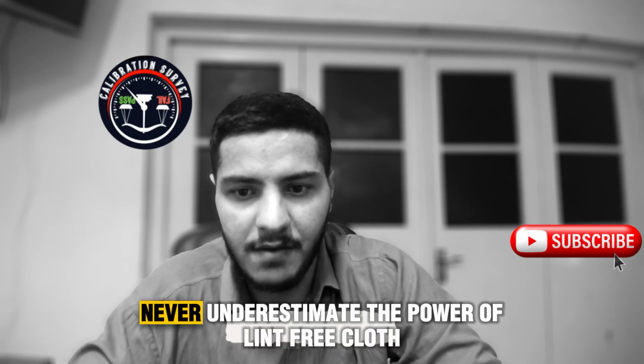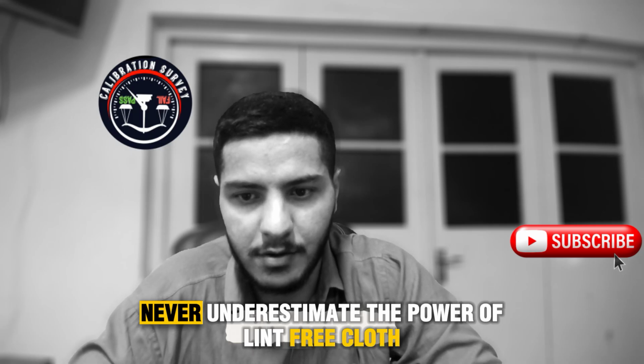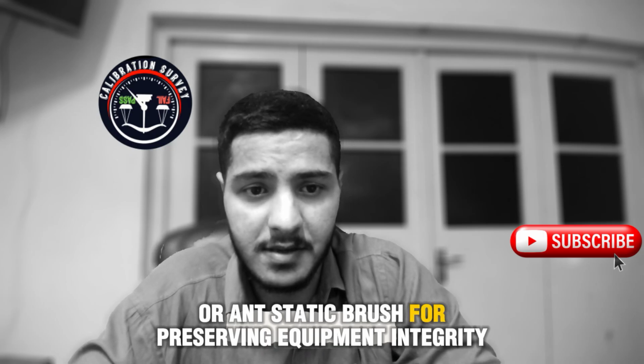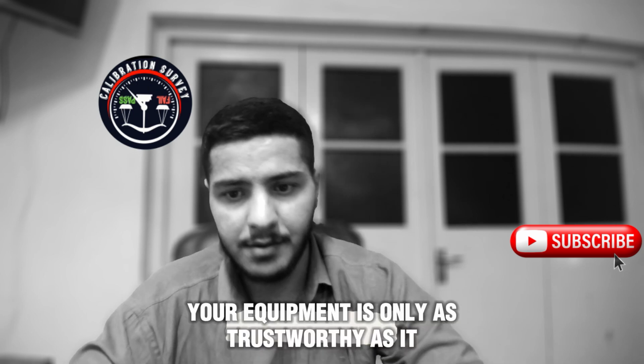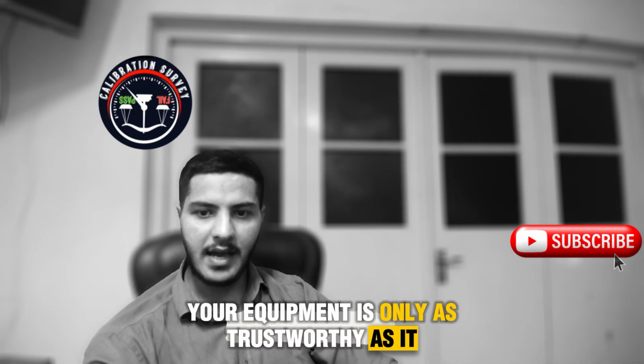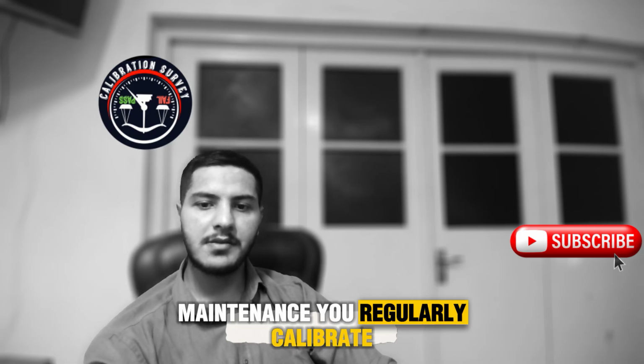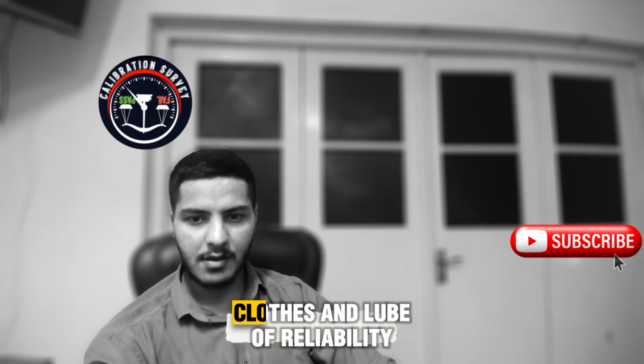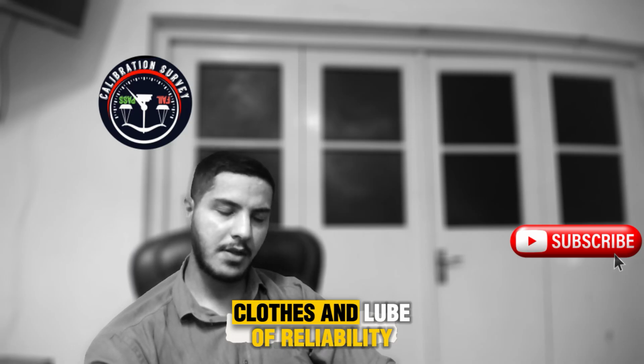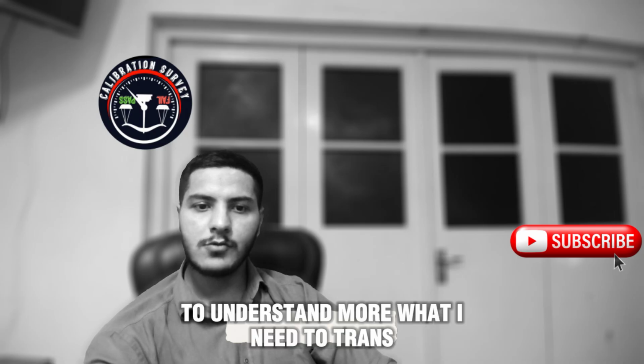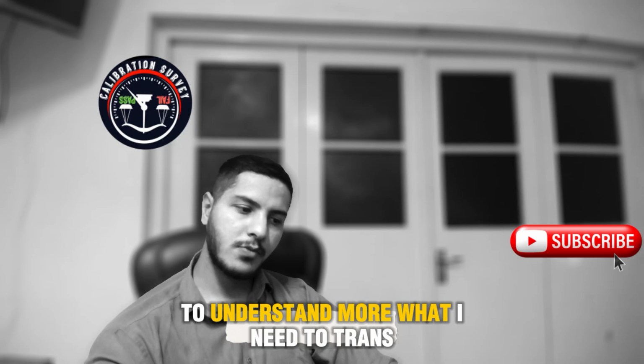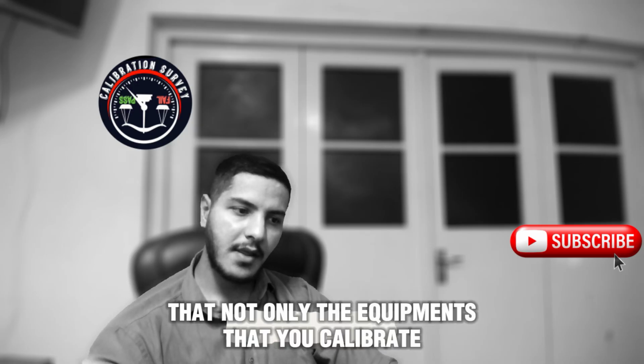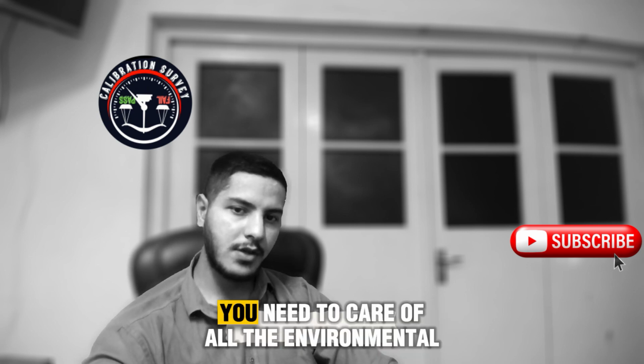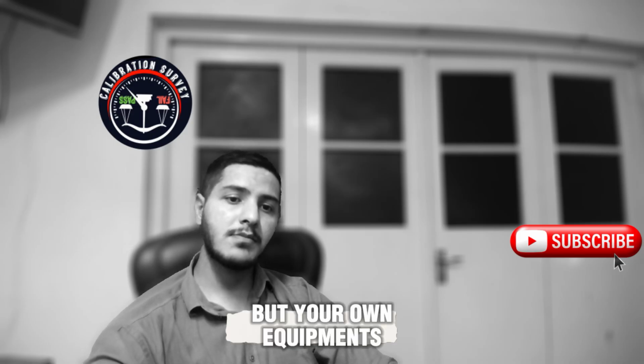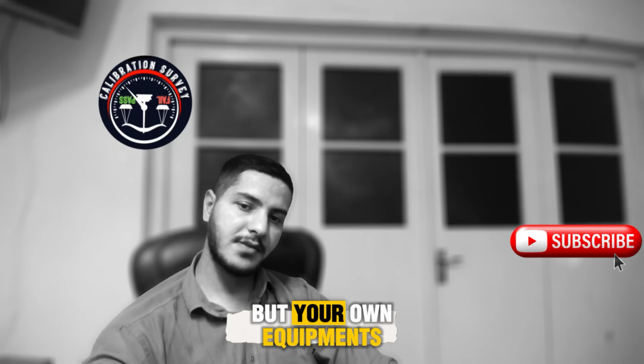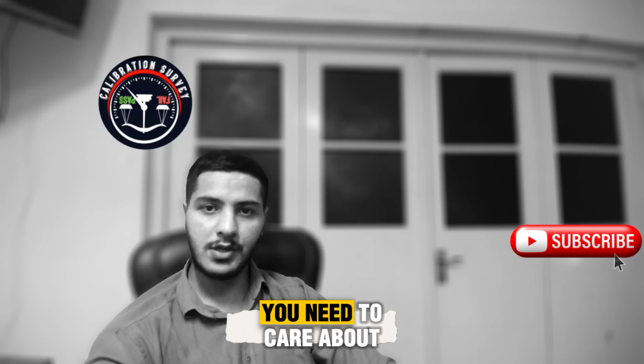Cleaning supplies. Never underestimate the power of lint-free cloths or a fine brush for preserving equipment integrity. Remember, your equipment is only as trustworthy as its maintenance. Regularly calibrate and care for your own reference standards, closing the loop of reliability. To understand more, you need to care not only about the equipment that you calibrate or the environmental conditions, but also your own instruments that you use to measure.